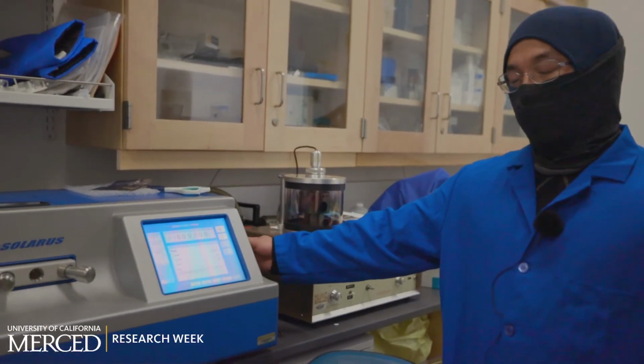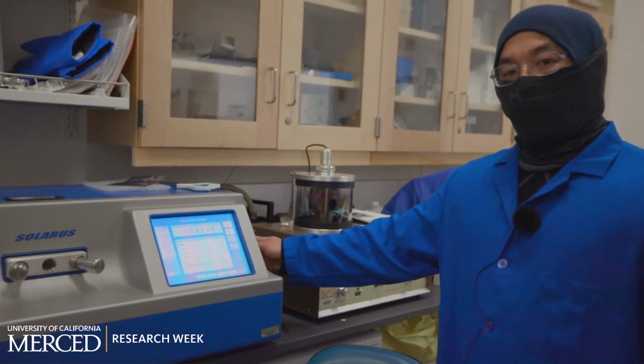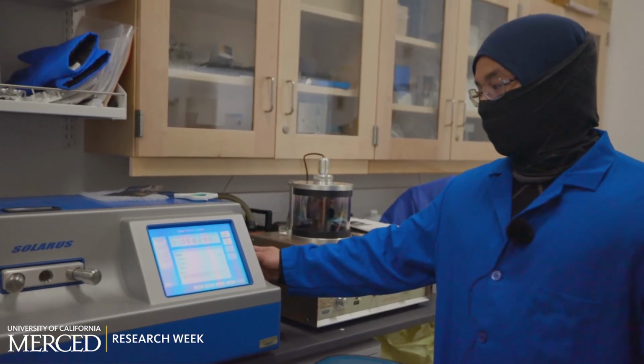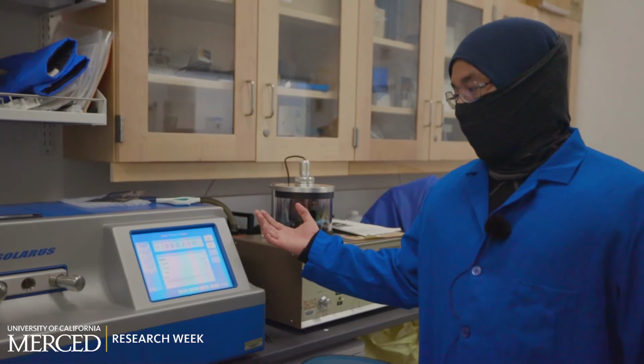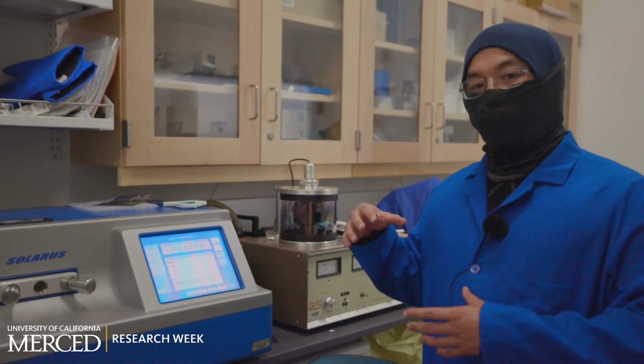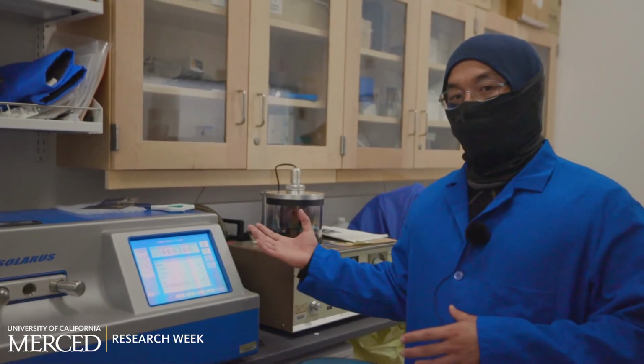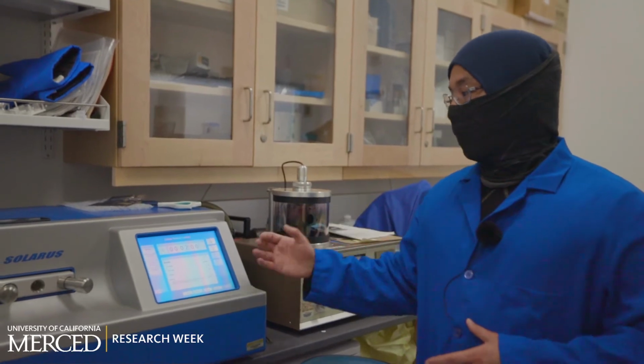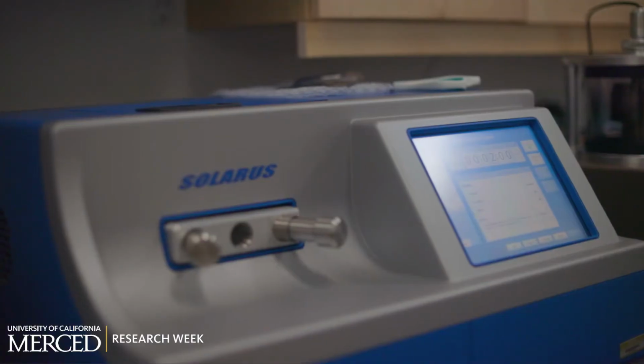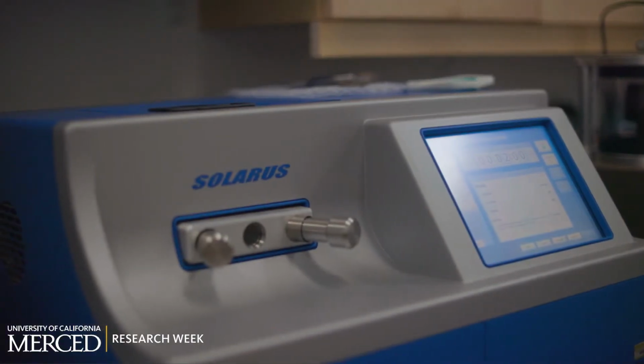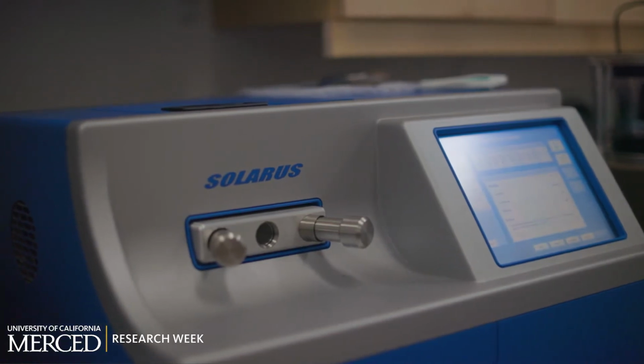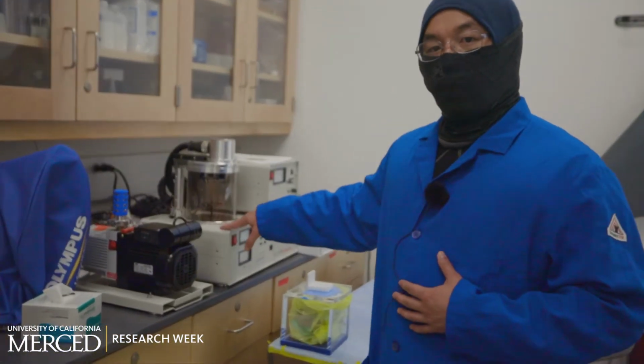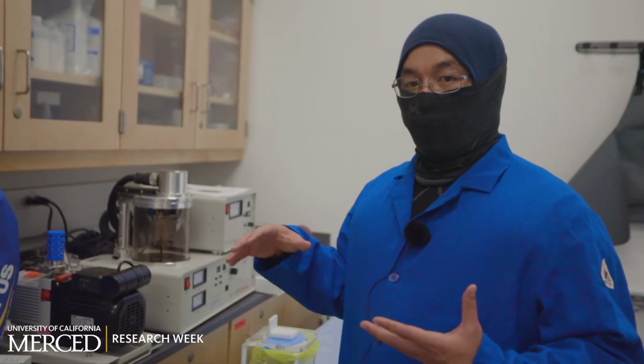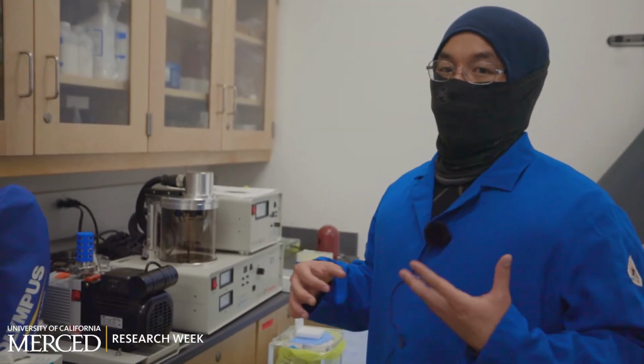This instrument here is our plasma coater. To add materials onto the different stubs or grid materials, we need to make them hydrophilic or hydrophobic. So this is how we treat our samples with different gases, oxygen, hydrogen, argon, to treat the sample surface so we can analyze the sample as well. This machine over here is our carbon coater. If the sample is not conductive, then we could add a thin layer of carbon coating on top of it to make it more conductive for electron microscopy.